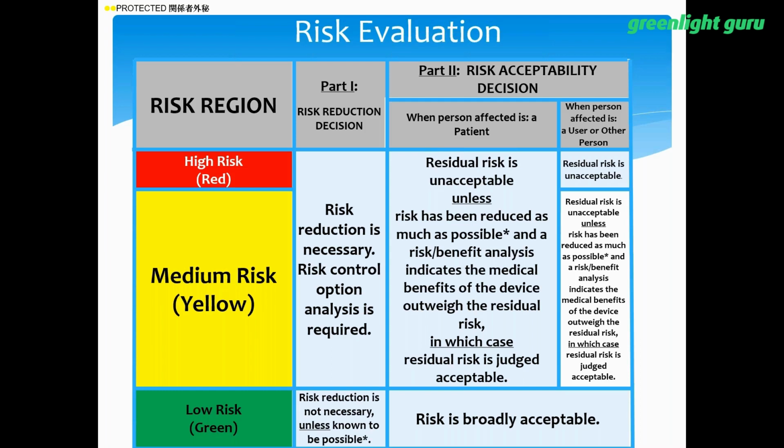In that particular situation, you basically want to say, if I can do it, why not do it if it's going to reduce that risk? Many times when you are in that green region, you're talking about things that are going to be a minor inconvenience or other things that may adversely impact your brand. It may not be impacting the safety of the patient, but again, this is where you have one of those issues that may come into play. When we're in the low risk region and the person affected is a patient or other than the patient, then that risk is deemed to be broadly acceptable.